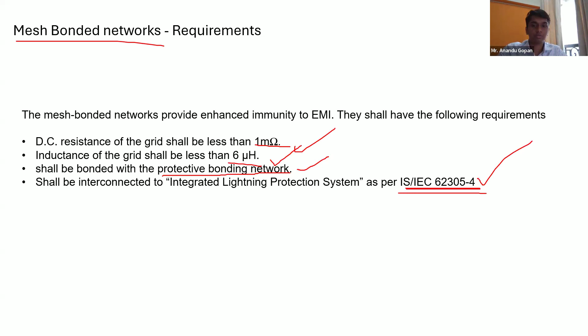Before I go into the mesh bonding system and the isolated mesh bonding system, I will just give a definition. This is as per ITU K.27, the general terms you will use in a mesh bonding system. You have your common bonding network. Common bonding network is nothing but effective bonding and earthing inside a telecommunication building. Basically, you have your metallic components, intentionally or incidentally interconnected. All your metallic components are connected. It can be interconnected, it can be looped. In some places, you are not supposed to loop. So basically, they are connected to form a bonding network.